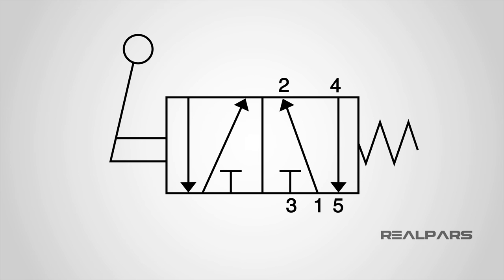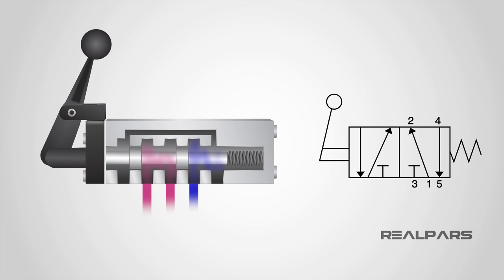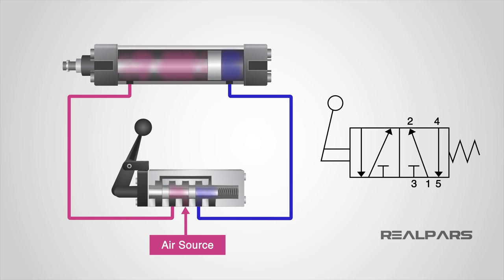Let's look at an example of a typical two-position valve schematic. This valve is controlled by a manual lever and has a spring that returns the valve back to the start position when the lever is not being operated. The current state of the valve is shown by the box immediately next to the active actuator. So in the case of our example, if the lever on the left is not operated, the spring return actuator on the right side is controlling the valve, so we can look at the blue box to see the flow path and ignore the red box.